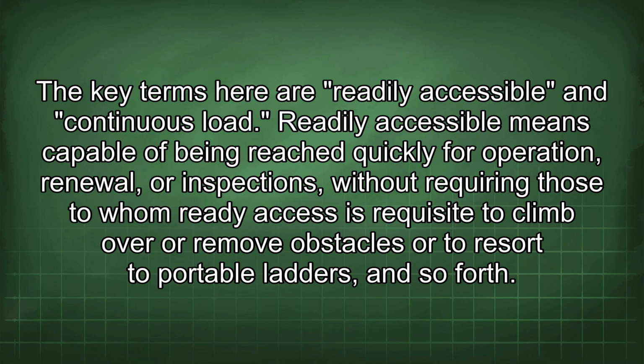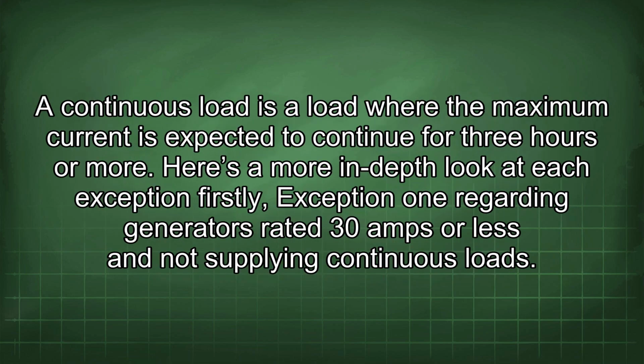Readily accessible means capable of being reached quickly for operation, renewal, or inspections, without requiring those to whom ready access is requisite to climb over or remove obstacles or to resort to portable ladders, and so forth. A continuous load is a load where the maximum current is expected to continue for 3 hours or more. Here's a more in-depth look at each exception.